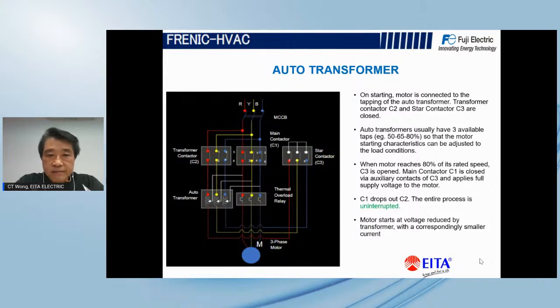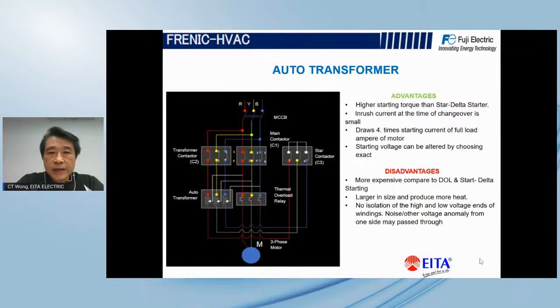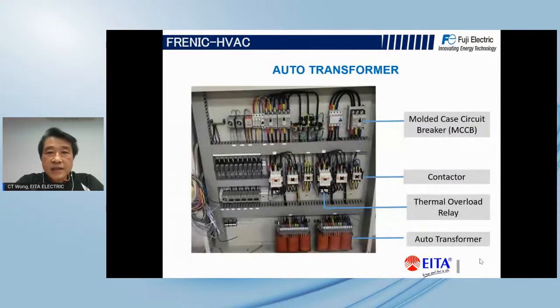From here, you can see there is only a 3 wire connection after the delta contactor cuts in, very close to the star delta. The advantages are that it is simple, but we can deliver high torque, and the inrush current can be lower compared with star delta. The disadvantages are that it is more expensive compared with direct online and star delta, and a bit bulky in size. Let us move to the picture. On the bottom part, you can see the orange-colored part is the auto transformer. This will be the actual picture of an auto transformer.